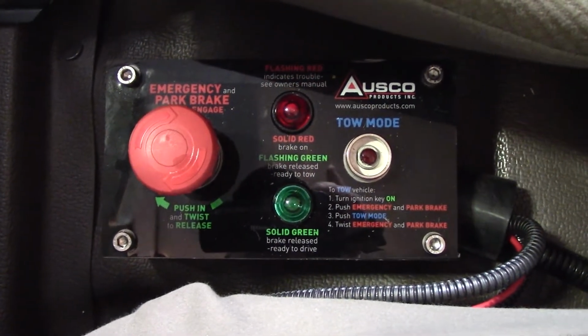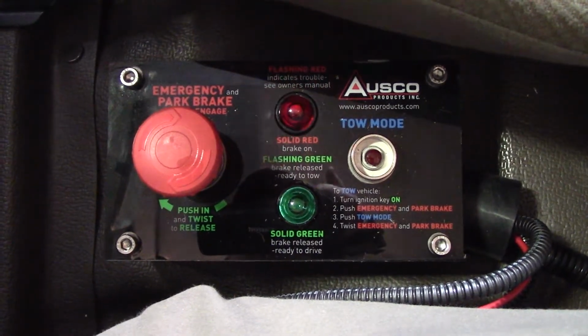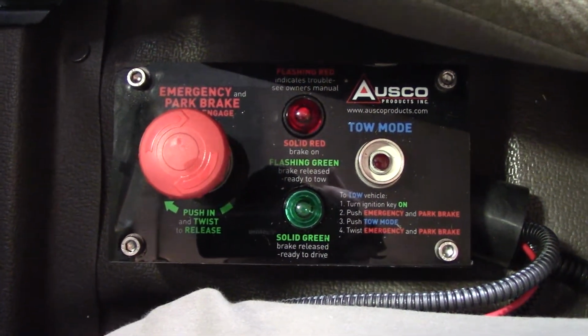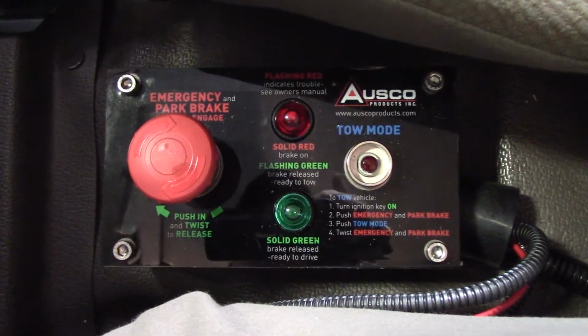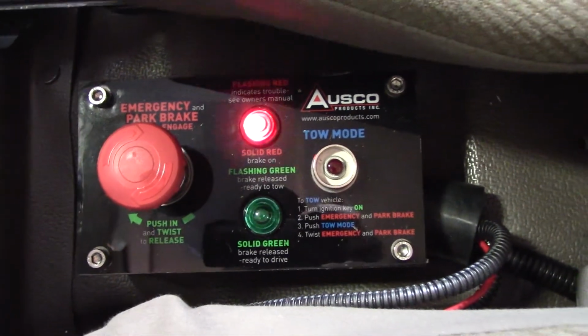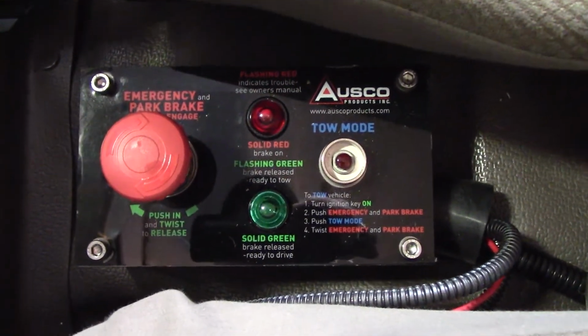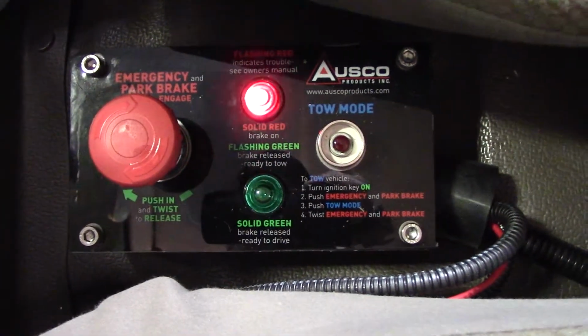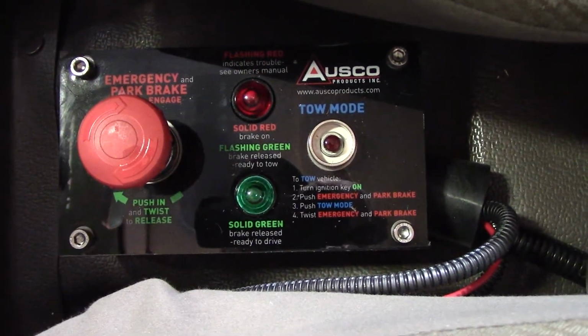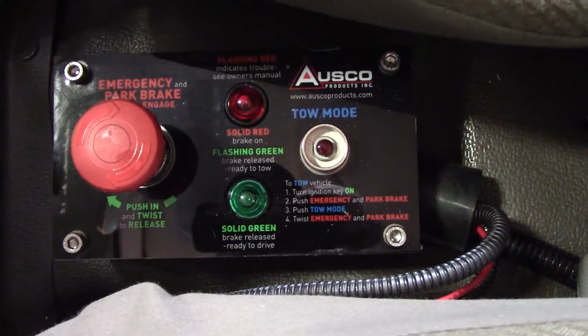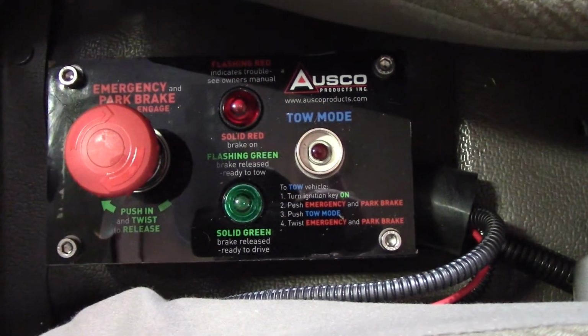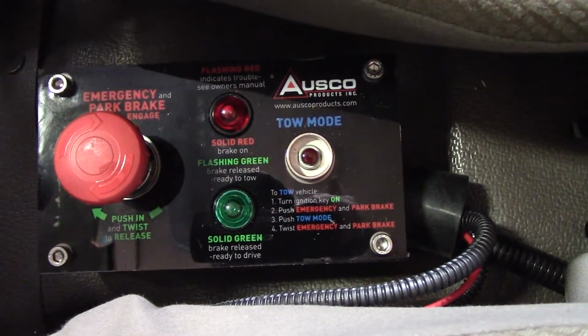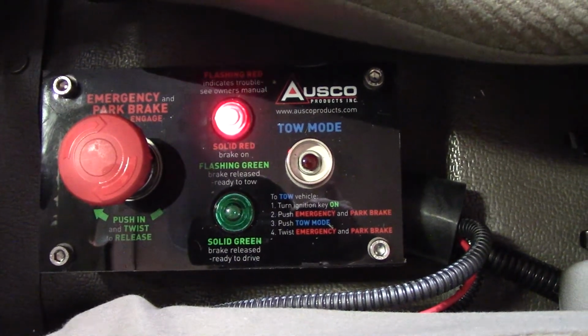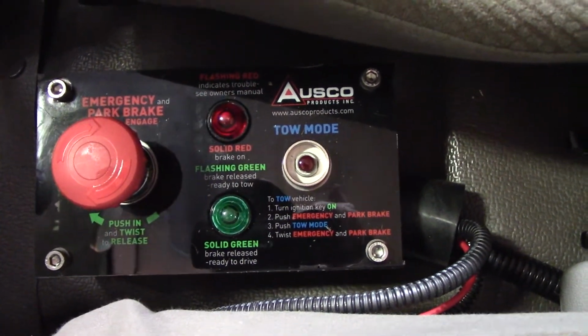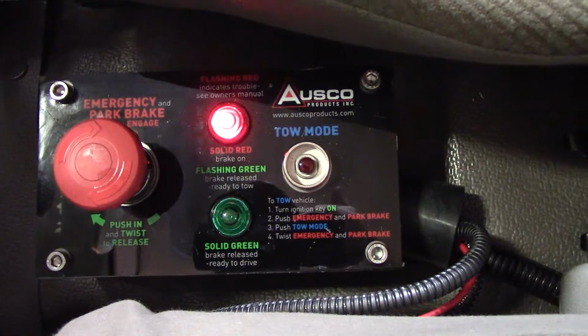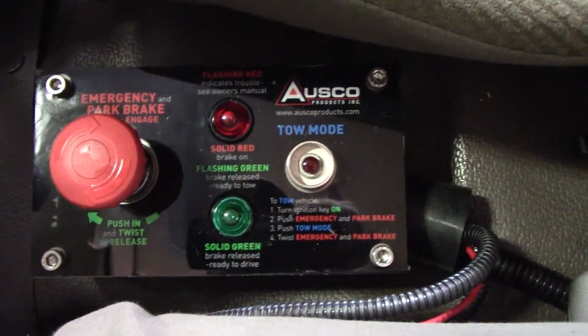Alright, so the second error code that we have is when the red light flashes 2 times, and that means that the system is not achieving hydraulic pressure within 30 seconds. So the problems with that could be either low fluid level in the pump pack reservoir, leaks in the hoses, brake tubes, or fittings. The system may have overheated, so you're going to want to remove the enclosure cover to allow the pump to cool.